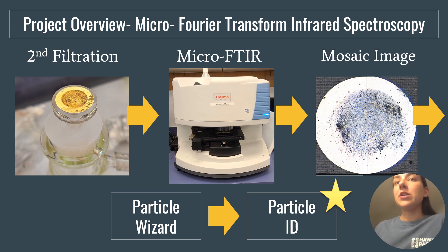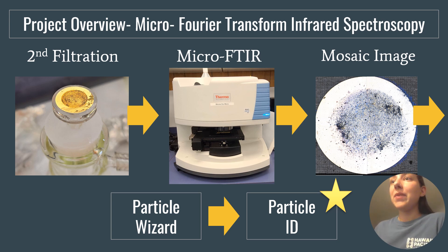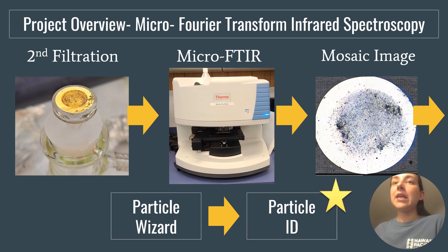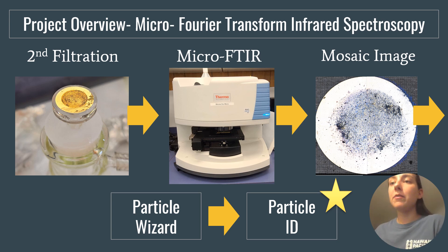The software used in this process will automatically compare each spectrum to a preset library with a variety of spectra, and will automatically identify the particles based on comparisons to the library spectra. The magic of automation is that rather than manually taking each spectrum of each particle, we can, after a few hours of waiting, get a complete report on all of the particles — on all of their identities and their size as well.